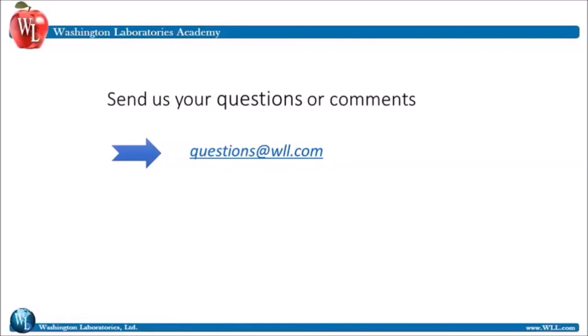Why does MIL-STD-461 not deal with CS 103, 104, 105, 106, and RE 103? Those are radio-specific elements, and they're just not accomplished on a large variety of equipment. There's a lot of information available about those tests through various reference materials. But I know, Mike, you left those out because they're not a common test. It happens on a small percentage of the overall test, and this is more of a high-level webinar. So I'm sure that's why we didn't try to cover those, just a time consideration. So I mentioned in the beginning, this could be a week-long course. Yeah, when I teach it, it's a week-long course.